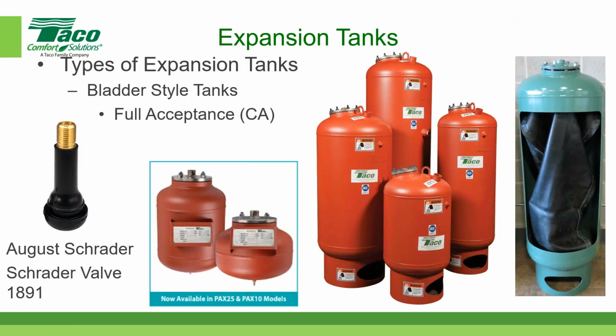So let's go back to the full acceptance. One of the things this particular tank has, which you can't really see in the photograph, is a connection at the top - a flange connection with bolts around it. They can be removed and this flange can come off, and the bladder can actually be removed off the top of the tank. So you can replace the bladder in this style tank.